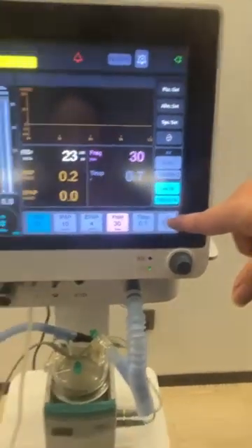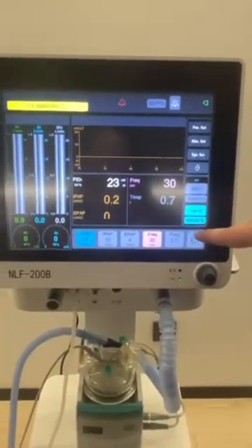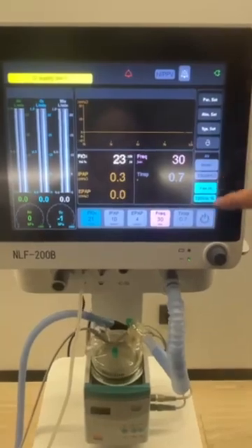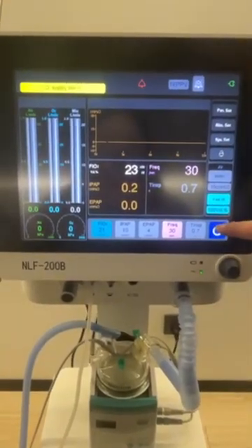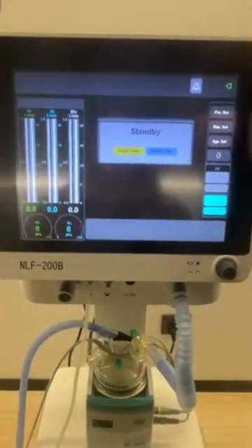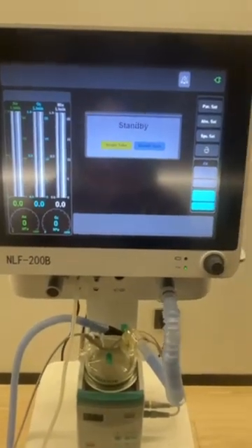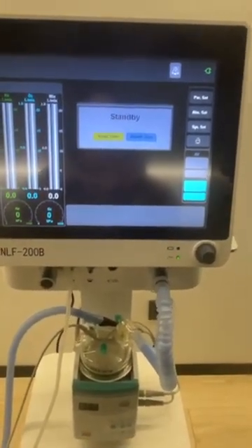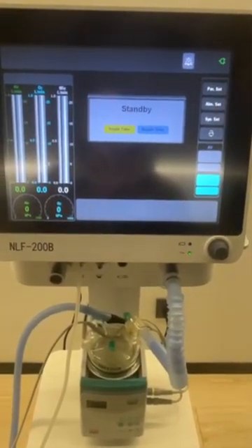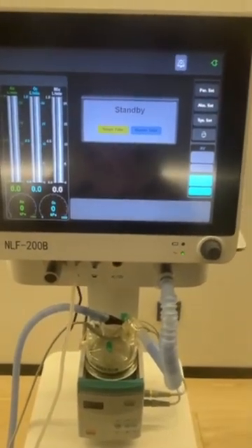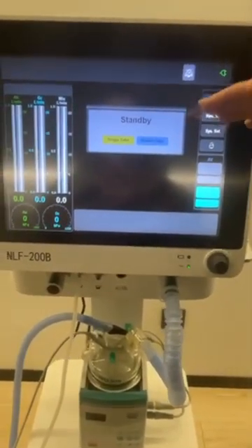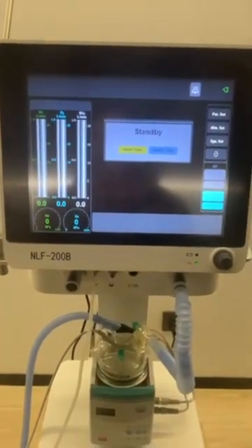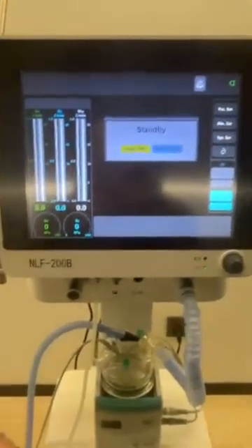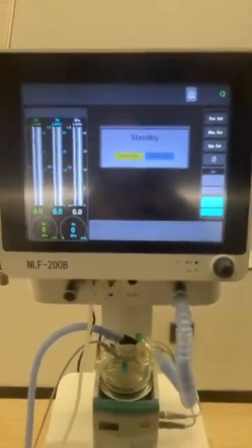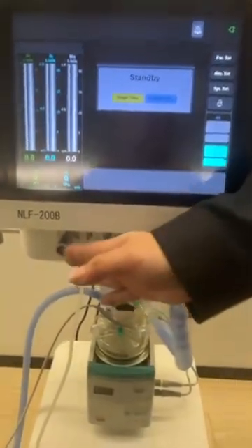Then the next button here, you can see once I press it, there is no response, because we have a design here. Only if we press it for 3 seconds will it enter the standby interface again. And by now, the ventilation has stopped. So only if the patient has finished using the machine, or we want the machine to have some rest, then we just get it back to the standby interface. And then we can power off as per your requirement. Both okay.